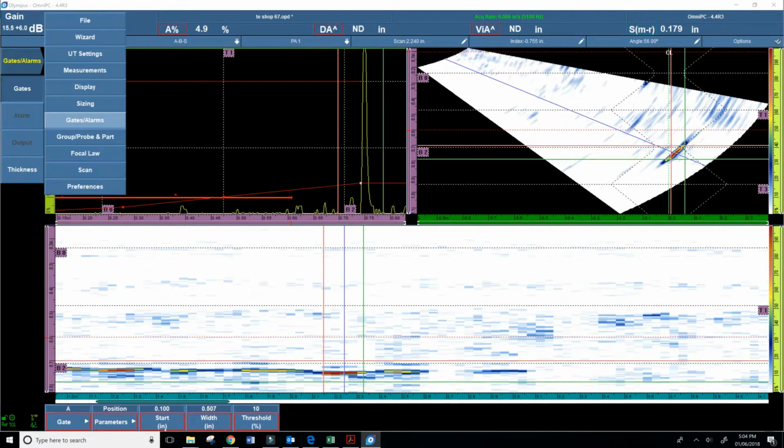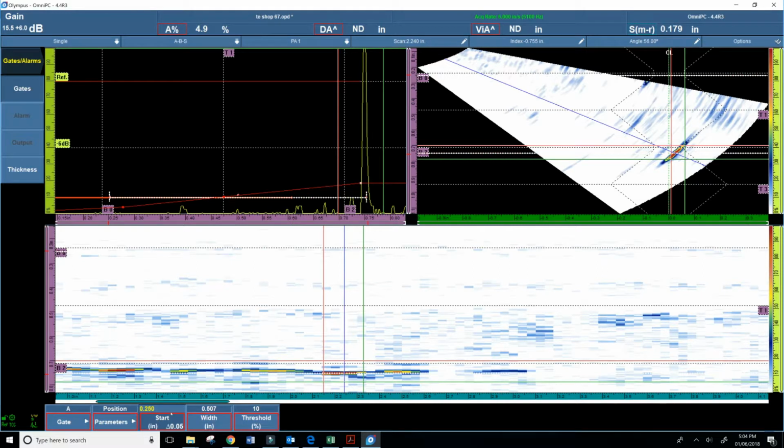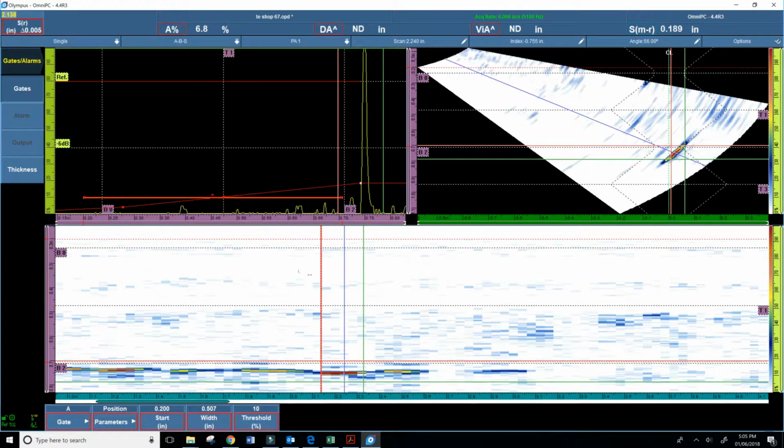That's the worst, and ranges and everything. So actually, yeah, we'll do a gate. So if I move this, I'm moving in 100,000ths increments, which isn't bad. I think the range defaults to a 1/2 inch. I never ever move the gate in or the range in 1/2 inch increments. It's crazy. Usually when I start a setup file, I have to go back through and change this.